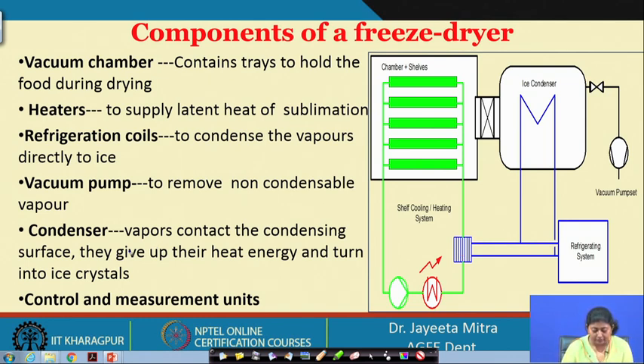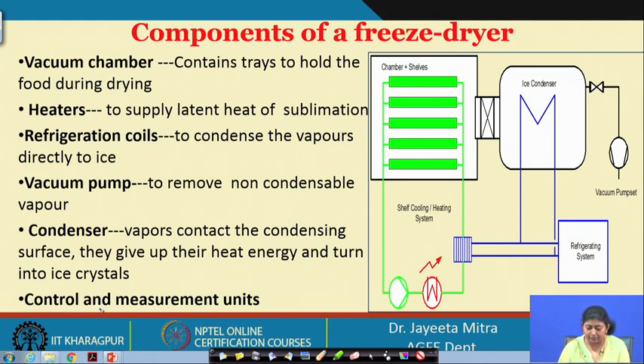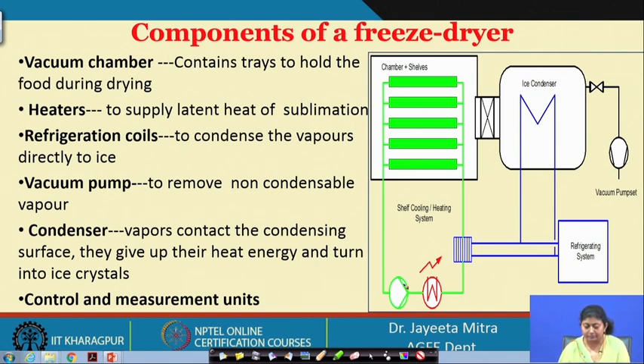Later, when sublimation occurs, the vacuum pump will operate to take vapors out from the chamber to the condenser, where they condense, and the vacuum pump runs continuously to maintain the lower pressure level inside the chamber. The condenser is used for condensation of the ice crystal — vapors contact the condensing surface, give up their heat energy, and turn into ice crystals. Finally, we need a control and measurement unit, because we need to maintain the temperature of the sublimation front, the source temperature (whether convective or radiative), the vacuum level, and the rate of heat transfer to the material.